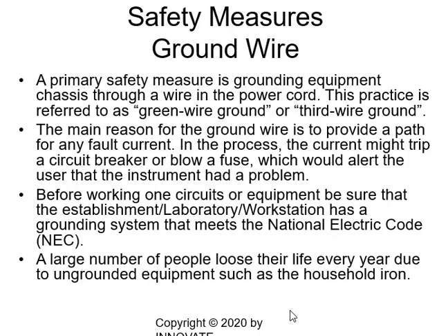wiring system in the establishment which meets the National Electric Code, or the NEC, because the whole system has to be connected to a grounding rod, which you dig deep according to the NEC, and you place it in and connect it to your household or to the establishment. The third wire in the cord or in the plugs is connected to this ground wiring system.